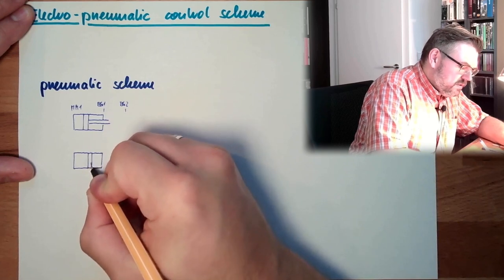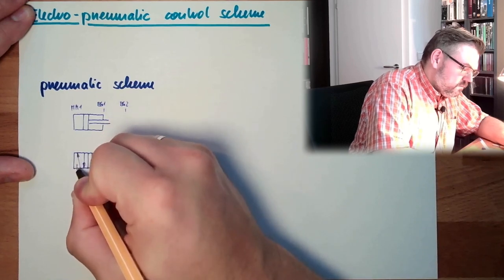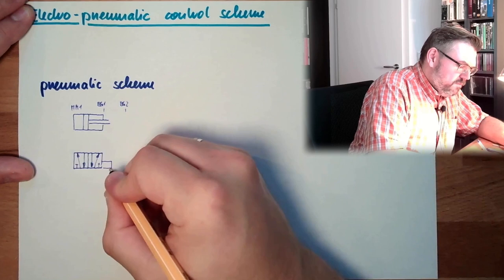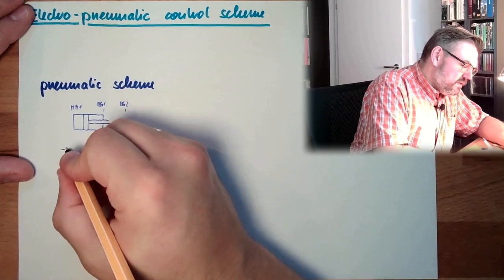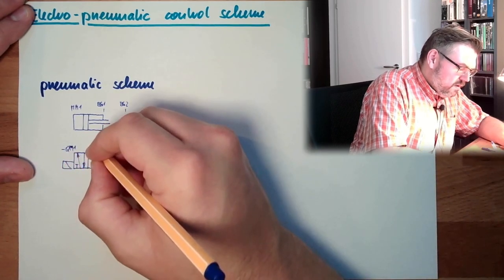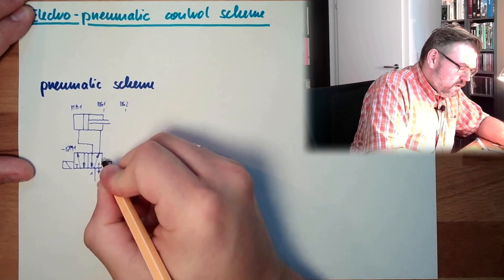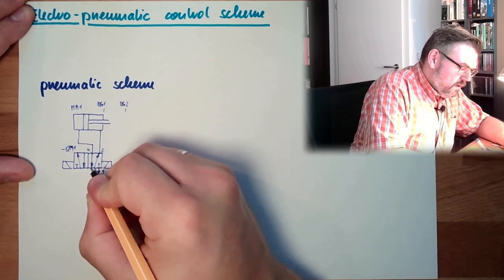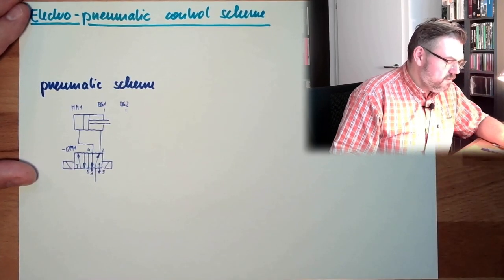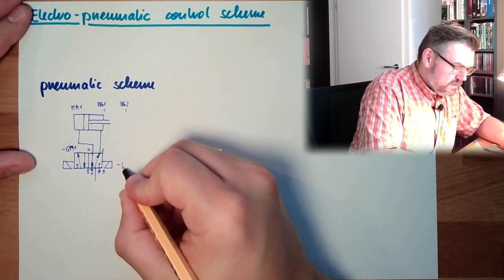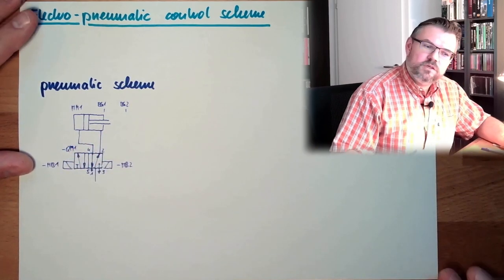It is a double-acting cylinder, so I need a 5-2 way valve. I will simply draw here directly the coils, even if it is pre-controlled usually. This has also a name, QM1 is the switching element. And here we are going to the cylinder. Here we have the 1 connector, 2, 4, 3, 5. This usually also has a name. So this is MB2 and this is MB1, the coils which are operating this.